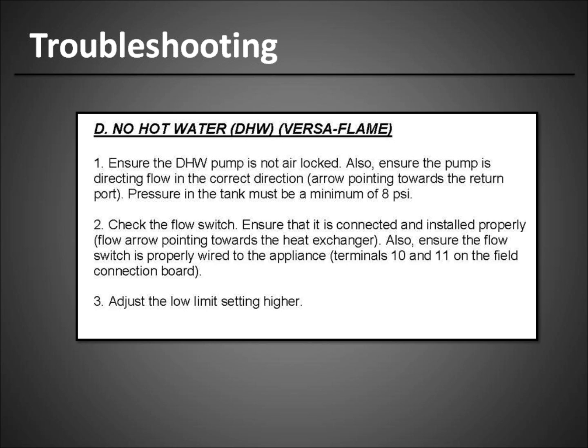So you got to make sure you have your domestic pressure, you have all that purged, and you got to make sure that you have at least a minimum of 8 psi on the hydronic loop.